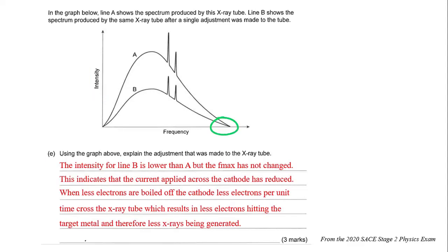This indicates that the current applied across the cathode has reduced. When less electrons are boiled off the cathode, less electrons per unit time cross the X-ray tube, which results in less electrons hitting the target metal and therefore less X-rays being generated.